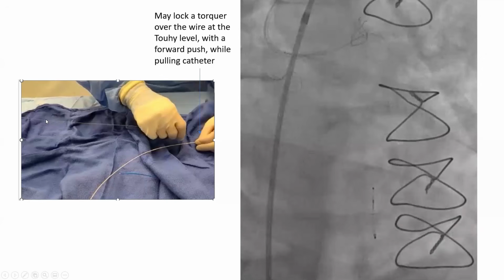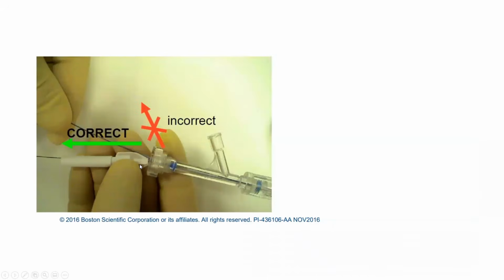Now, the spider wire is 300 centimeters, but you don't need the 300 centimeter. You can work the whole case in a monorail fashion, so you can break it at 180 centimeters. And actually, it is designed to have an area that can be broken at 180 centimeters. This is how you can put a torquer on the wire as you're pulling out the catheter. And normally, you try to pull the catheter while it's coaxial with the wire, so you get better force transmission.